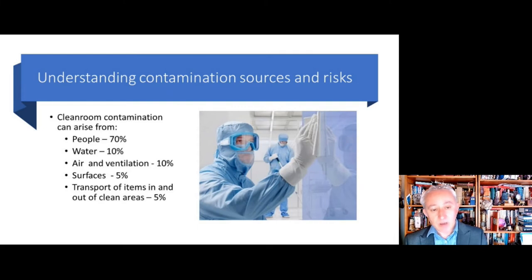A lot of that contamination is going to be coming from people. Survey after survey indicates that people are the greatest contributors to contamination within the pharmaceutical environment. What's on the slide are just some figures put together from different literature reviews. From industry surveys, people are contributing around 70% of the contamination. This is in a fairly generic idealized facility. Water, depending if there is a water source in the area, is around 10%, and water is both a vector for contamination and a growth source.